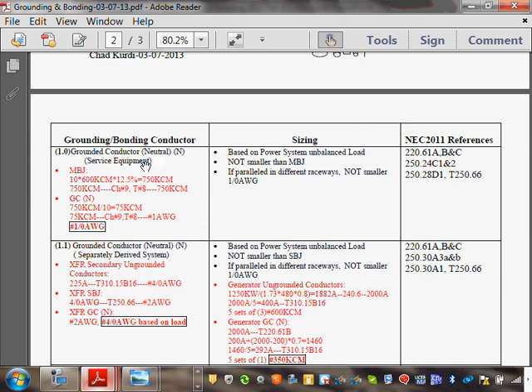It's called grounded conductor. Do we size it based on, here's all the references, based on the unbalanced load, if you know it. If you don't know it, not smaller than the main bonding jumper, that's a code. And if you're paralleling, like a 4,000 amp switchgear, you must parallel. No matter what you do, your conductor cannot be less than 1/0 when you parallel, right? You can't parallel less than 1/0 unless you're a power limited guy or gal, then you can parallel less than 1/0. You can parallel number 12 if you want to. Okay, so here's what we do, guys.